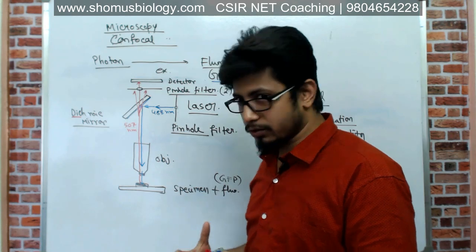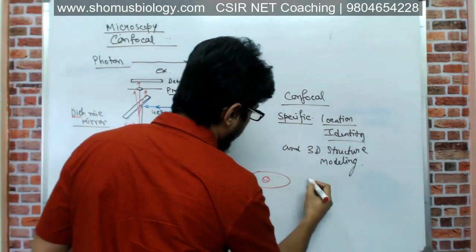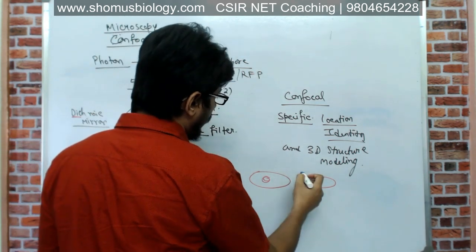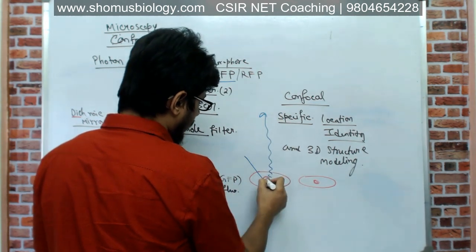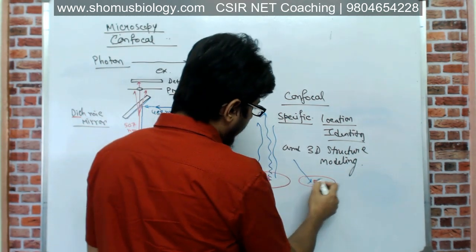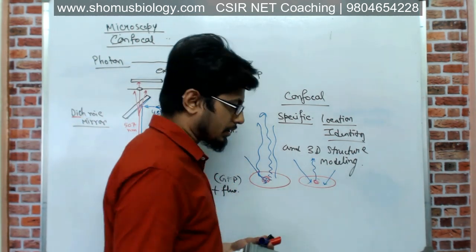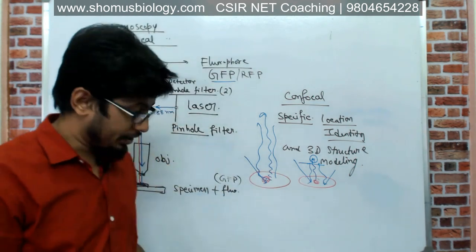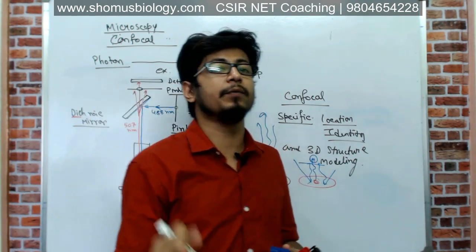In conventional wide field microscopy, light hits the cell and emission comes from different sides, all received by the detector. But in confocal microscopy, if we want to visualize only the nucleus, the other emissions from different parts of the cell are cut out and only the emission from the nucleus is received. The nucleus may be at the top or bottom of the cell at different depths — we can achieve that precise targeting with laser.